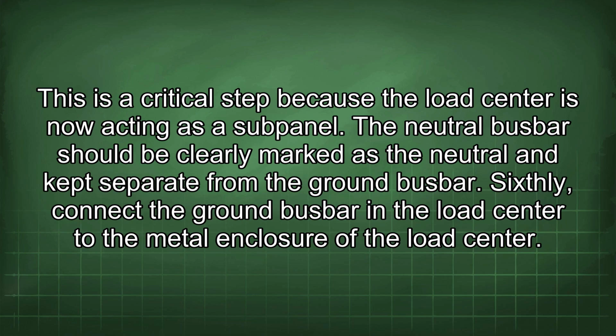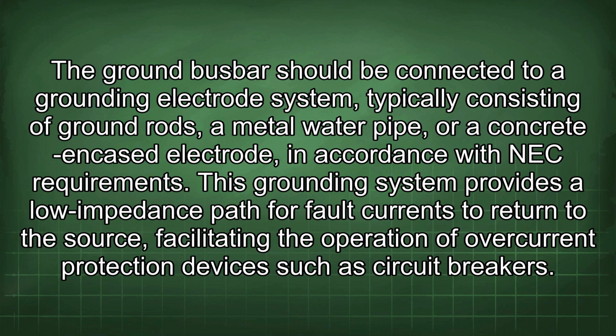Sixthly, connect the ground busbar in the load center to the metal enclosure of the load center. The ground busbar should be connected to a grounding electrode system typically consisting of ground rods, a metal water pipe, or a concrete encased electrode, in accordance with NEC requirements. This grounding system provides a low impedance path for fault currents to return to the source, facilitating the operation of overcurrent protection devices such as circuit breakers.